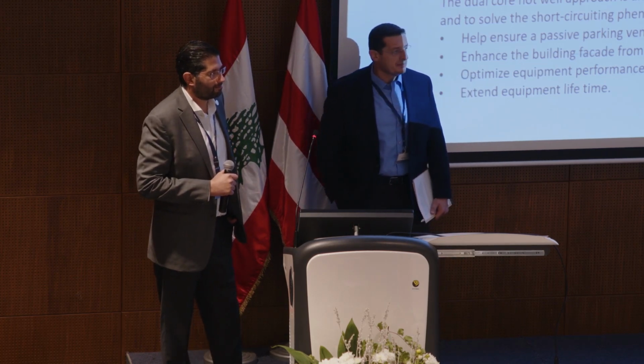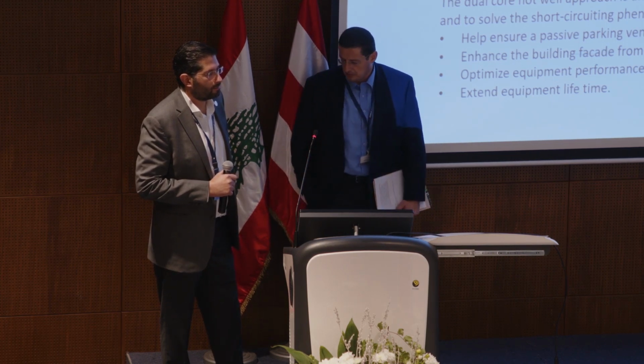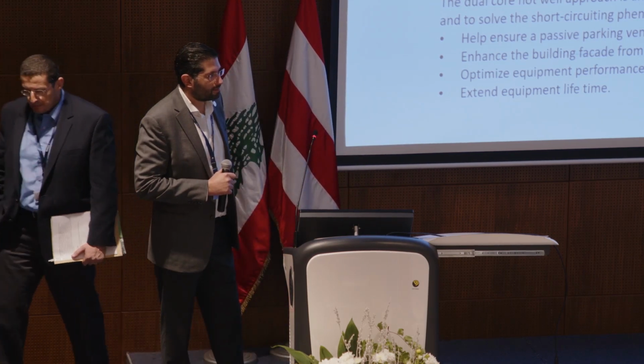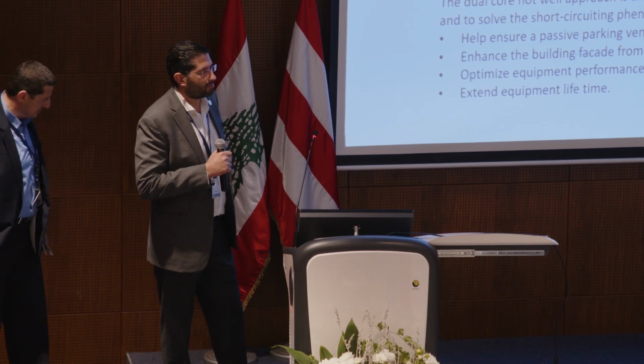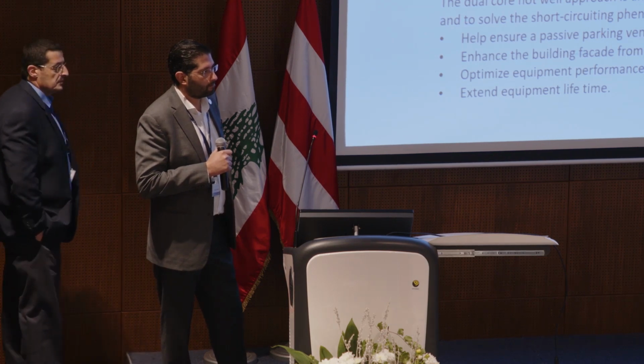Thank you, Ibrahim, for the presentation. It's quite interesting, actually. The idea of the condensing unit, I totally agree with this. We already did this like 7 or 8 years ago in Kfuri building Demco, Nantes, if you know. I was with a contracting company back then, and it was VRF units. But we did louvers, and we did CFD calculation, and it's working just fine. The performance of the units is quite good until today.